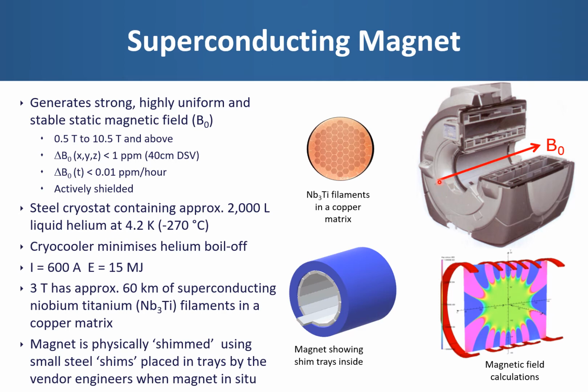A typical 3T magnet probably has approximately 60 kilometers of niobium titanium filaments, which are embedded in a copper matrix. The copper is there because in the event of the magnet ceasing to be superconducting, which is often referred to as a quench, that large energy store will be converted to heat, and the copper will conduct the heat away, hopefully without melting the magnet and irretrievably damaging it.